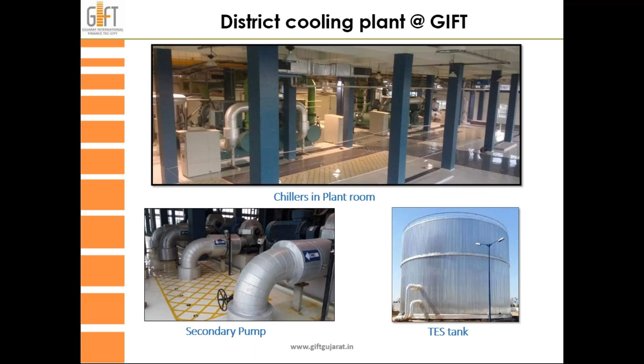What exact benefit are we taking from the DCS? With good engineering, one benefit is you can reduce your power requirement straightforward. Apart from that, by use of high COP chillers you can save energy; with higher chilled water temperature difference, you can reduce your pipe size and pump power. We use VFDs for chillers and VFDs for cooling towers. Very essential is pre-insulated chilled water piping, because the chilled water network is quite huge when you go for a DCS system.